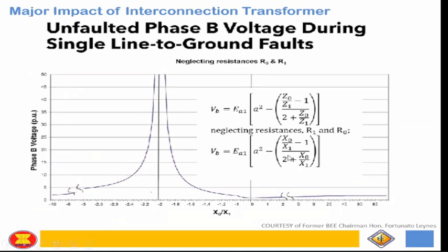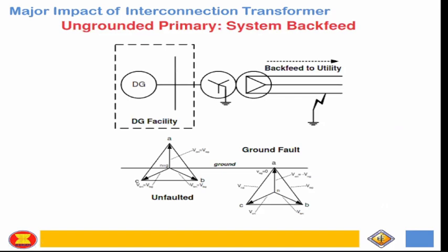And then there's a tendency because we all know that any variable divided by 0 magiging infinite siya. So at this graph, nagiging -2 siya, infinite yung overvoltage niya. Okay? Yun yung pinaka-worst. But there's really a tendency na mag-overvoltage talaga at certain ratio. Okay? So and by rule of thumb, parang nagsi-shift yan, no? From phase A fault shifted to ground yung A, then this magnitude ito, that's square root of 3.